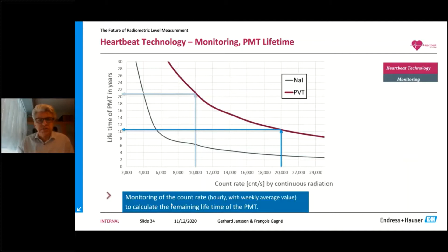So in my case, it would be good. I would have retired by that time, 20 years from now. So it would be a good time. If I then have a higher radiation to my detector, it will generate more counts per second, and now I will have a lower expectation. And as you see here, if I have a very, very high dose rate, I will really decrease the life expectation. So this is important to be aware of. And this heartbeat monitoring makes this relation very, very obvious.